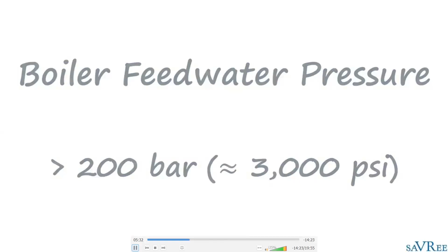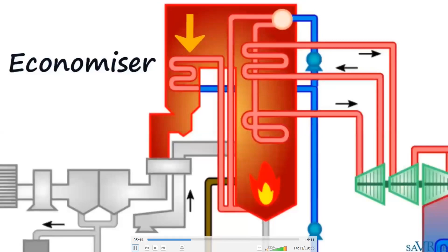The water will be pumped to an economizer where we'll preheat the water a little bit. Somebody was asking earlier about the economizer. Yeah, this is its function. You'll have to preheat the water before it goes to the boiler, and it happens in the economizer. It can also get heat from the flue gas before the gas leaves through the chimney. We send it to the main body of the water tube boiler. So the economizer is a nice way of preheating the water before we send it into the main part of the boiler to really start heating it up a lot more.